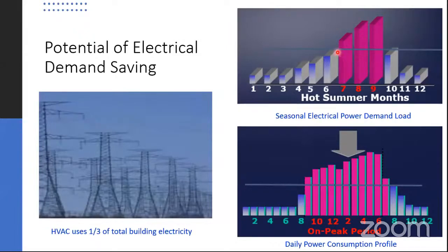This is also possible to actually cut the demand, that we can have chillers installed of lesser capacity and use thermal energy storage, like we did in the other case, in the hourly load pattern. This is for a daily consumption profile, and this is the seasonal electrical power demand load. As we all know, HVAC uses nearly one third or even more of the total building electricity.